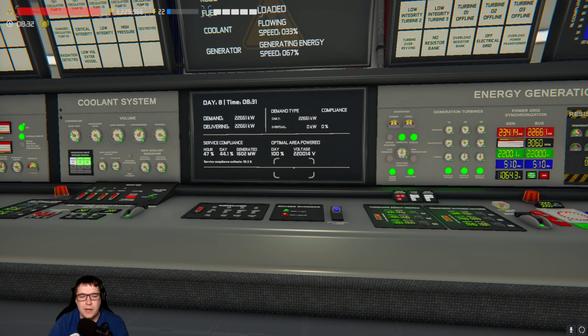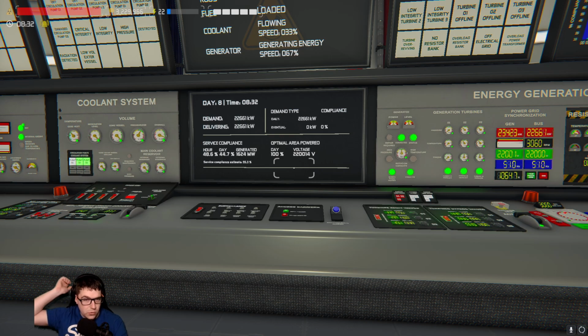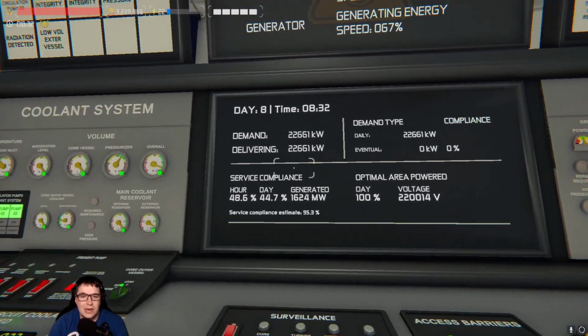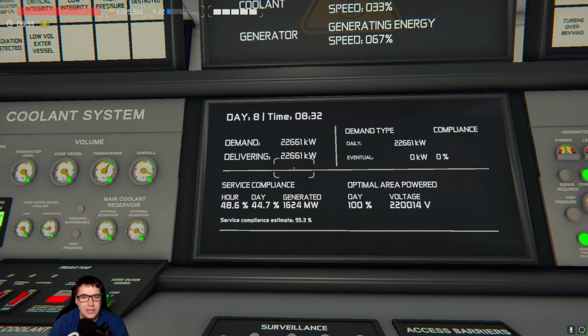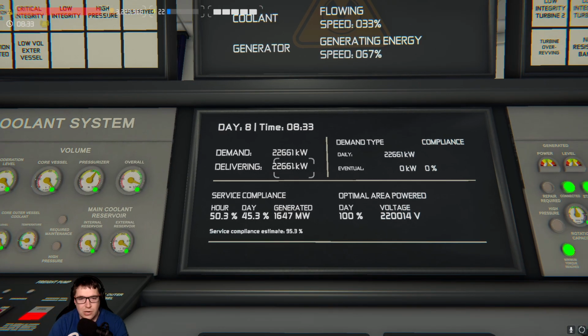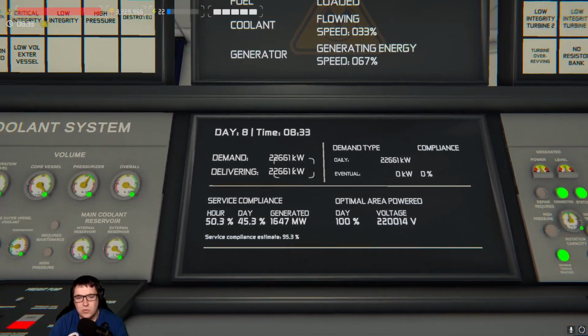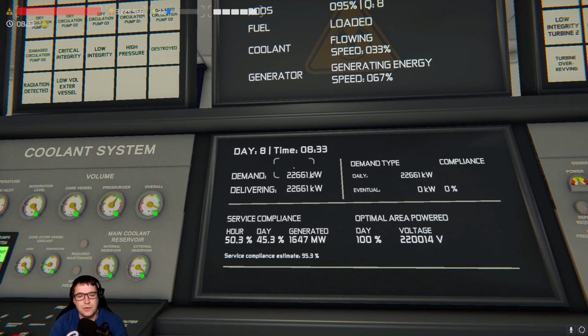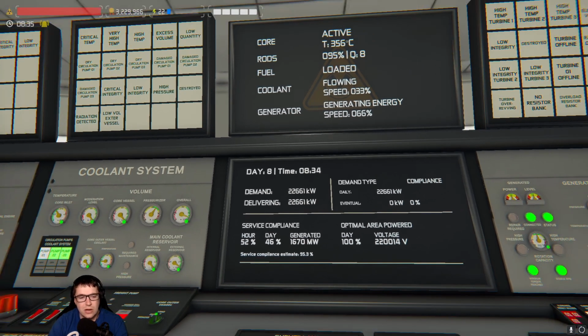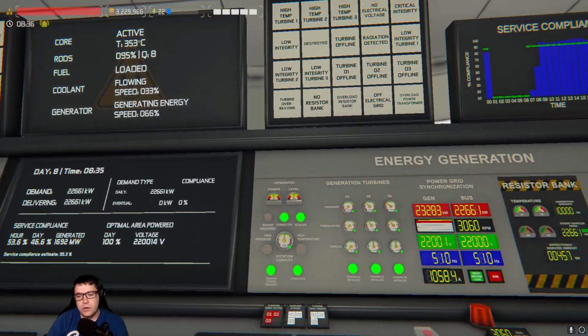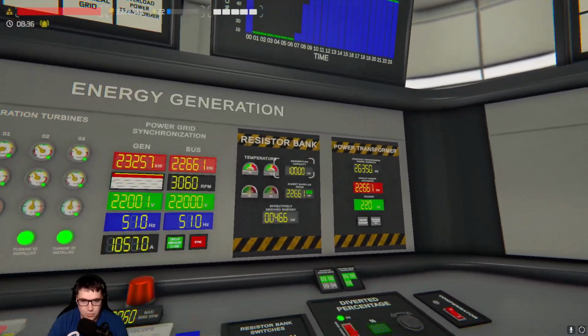So what do we do now, you may think? The demand that the power plant is asked of does change, on a daily basis and on an hourly basis. Once this goes past 9 o'clock, this will start to increase, generally up until about 2 o'clock in the afternoon, where it then tails off and it's almost down peak. Then when we're in the overnight period, early hours of the morning, it's quite low. So we're constantly having to make adjustments to the reactor to ensure we're keeping up with demand, but also ensuring we're not putting too much out and burning up the resistor bank.